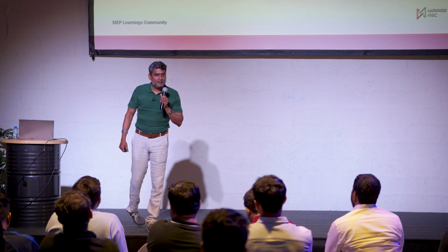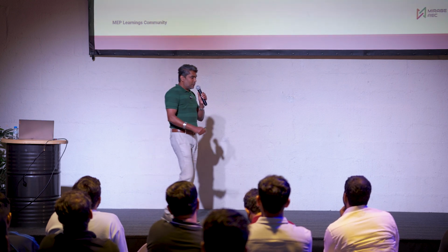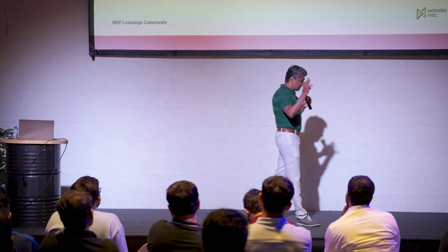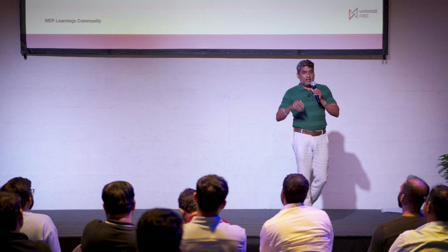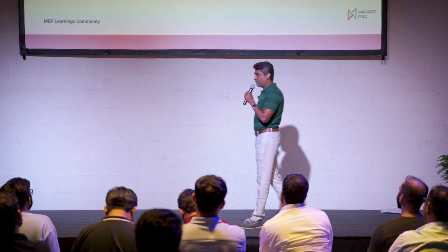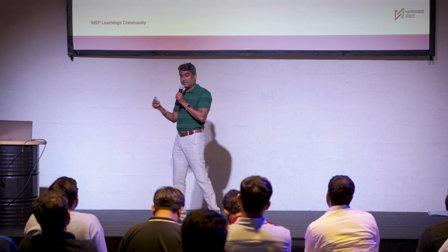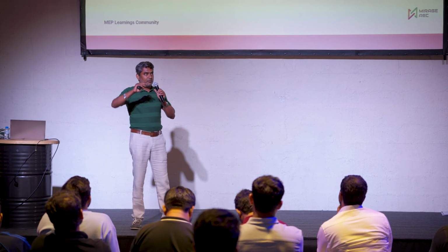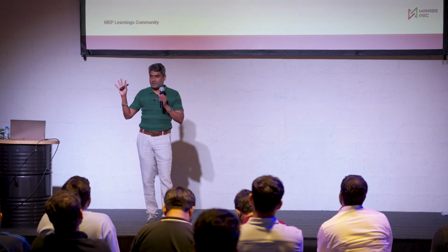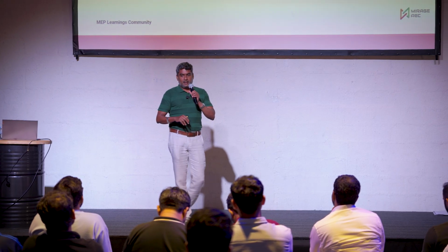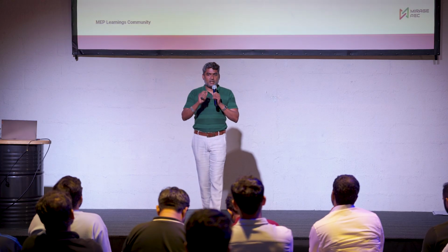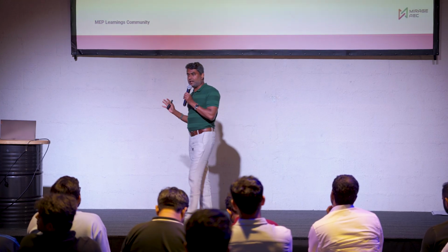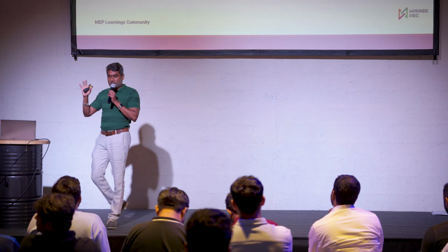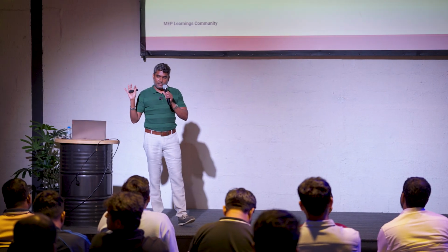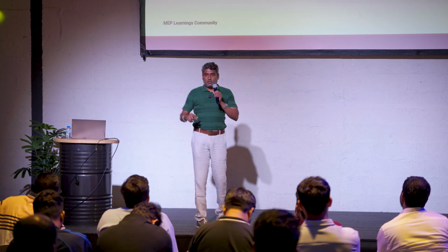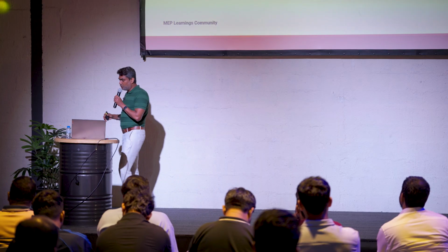Exactly. So when a sprinkler bursts somewhere in the building and water starts flowing in that sprinkler pipe, the flow switch captures that. The flow switch senses that water generally remains stagnant in the sprinkler pipes, so when water starts flowing, the flow switch gets activated. It's interfaced through the interface unit to the fire alarm system, so the fire alarm system knows there is flow in the pipe, meaning there is obviously a confirmed fire. So that's one - fire pump. I guess that makes the whole thing.